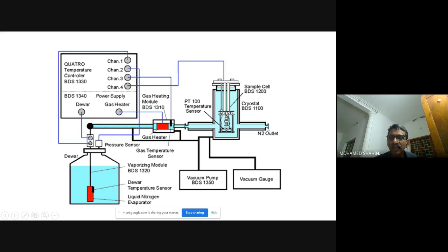So what we do is, you connect the pipe and keep it outside the room, so that the nitrogen gas will be going outside. And second thing, if some sample inside is a dangerous sample or carcinogenic sample or hazardous sample, the gas would be going out. That is the reason why if you go to any laboratory, you will see that there would be something connected to outside.